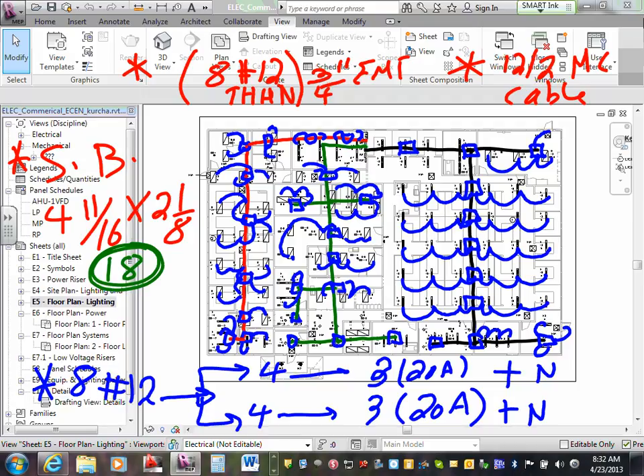So 3/4 of an inch. I told you guys, between the fixtures, we're going to use 3/4 of an inch, 8 conductors number 12, and we're going to use 12 MC cable. So here's what I would do. One way of doing it. I would start right in this area.